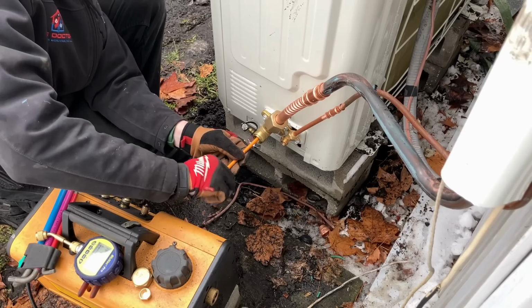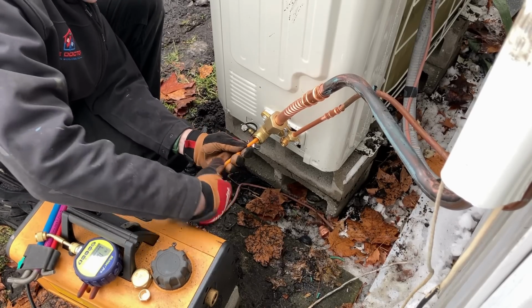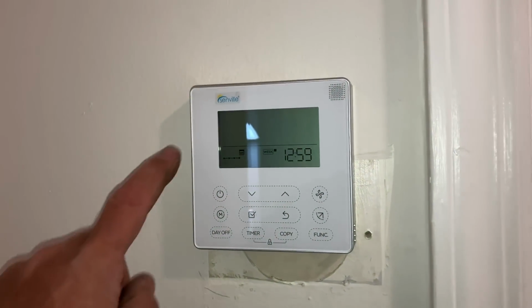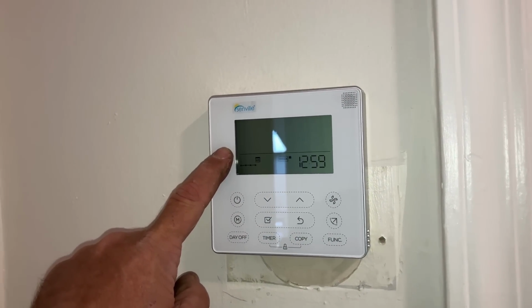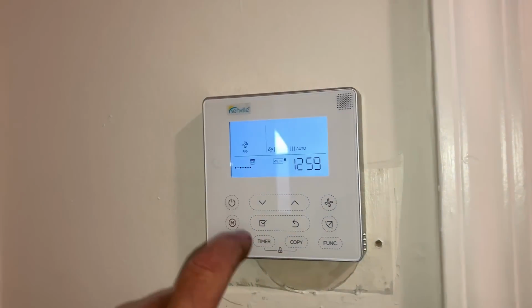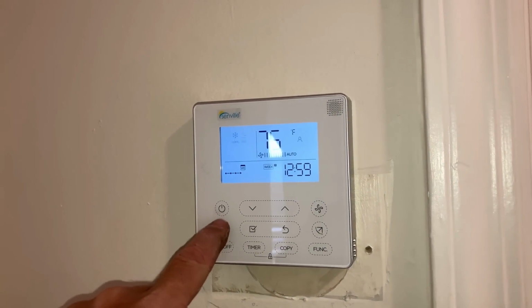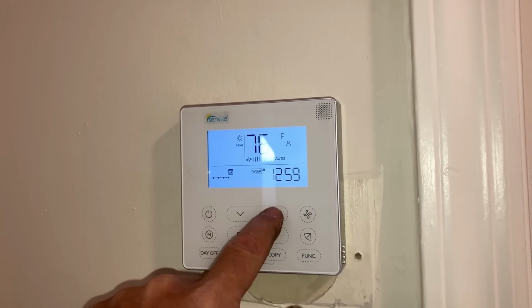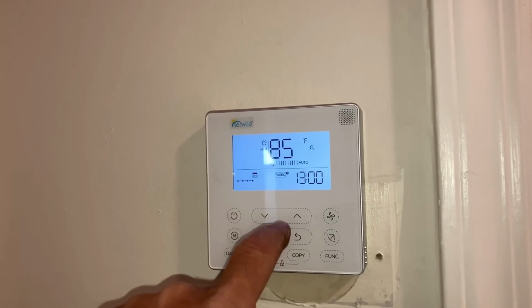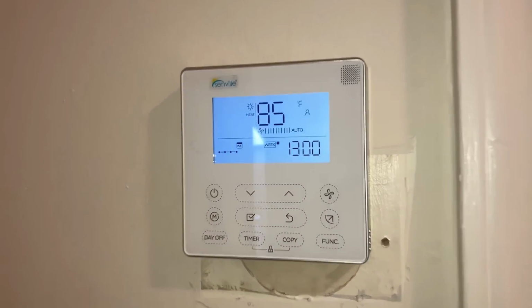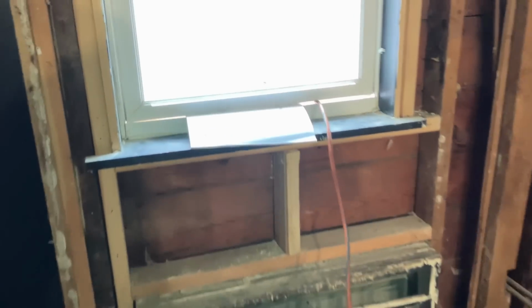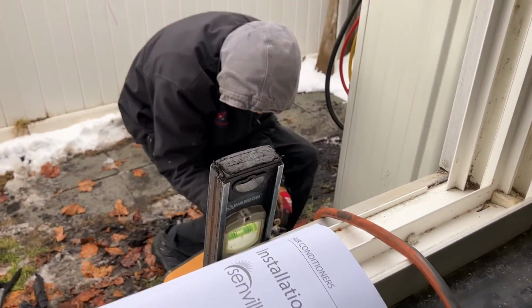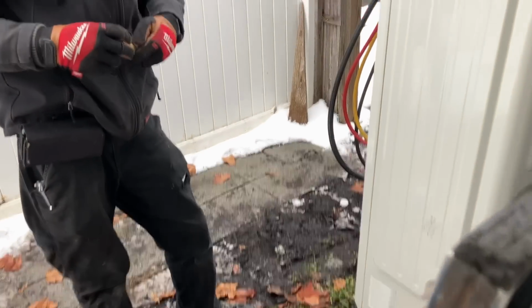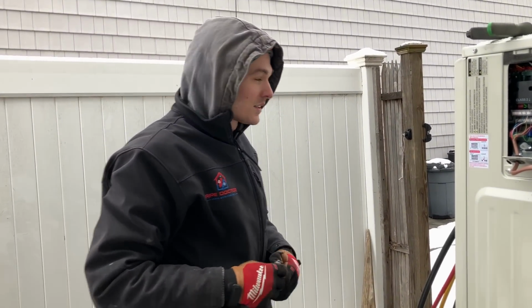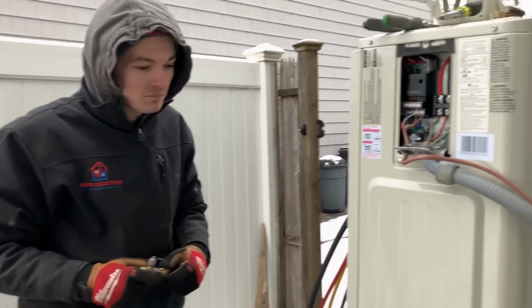And once power is restored to the outdoor unit, we're going to cycle the system in heat mode and fire up. All right, we put the thermostat in 24-hour mode. Let's power on. Let's change the mode to heat. And let's raise the temperature. Let's go to 85. All right. Get going. Excellent. The thermostat is set to heat mode and it's set to 85 degrees. Beautiful.